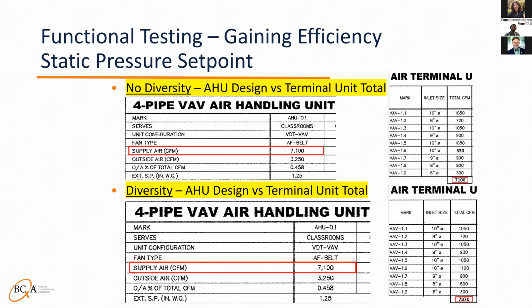So to set up your system to check the static pressure set point, total the box max cooling set points and make sure it is equal to the AHU CFM. Keep in mind you are commanding the terminal units to max cooling airflow set point. You are not commanding the damper to 100% position.